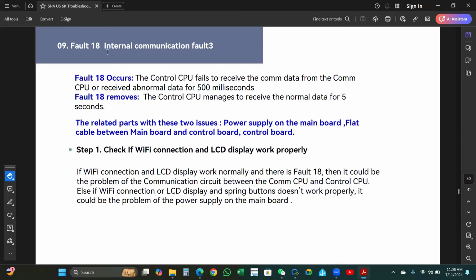Number 9, fault 18, internal communication fault 3. Fault 18 occurs when the control CPU fails to receive the COM data from the COM CPU or receives abnormal data for 500 milliseconds. Fault 18 removes when the control CPU manages to receive the normal data for 5 seconds. Related parts with these two issues are power supply on the main board, flat cable between the main board and the control board, and the control board.